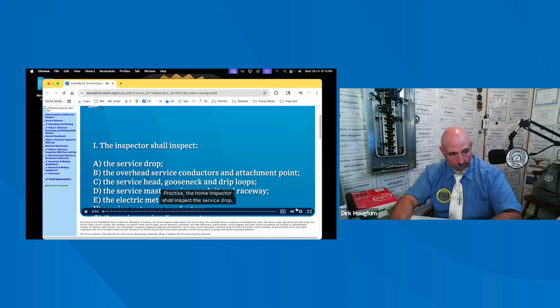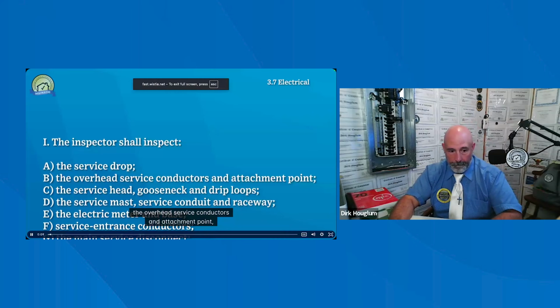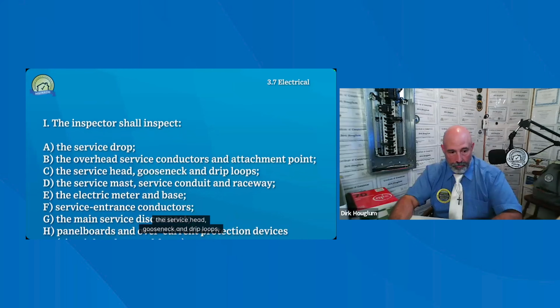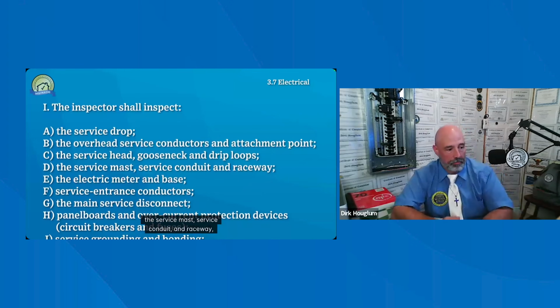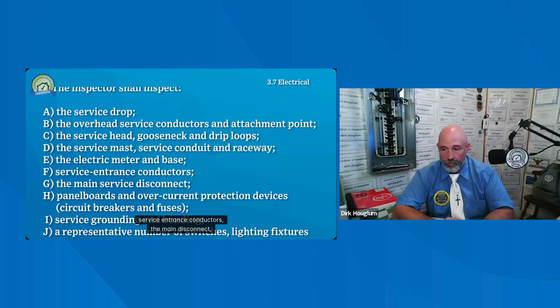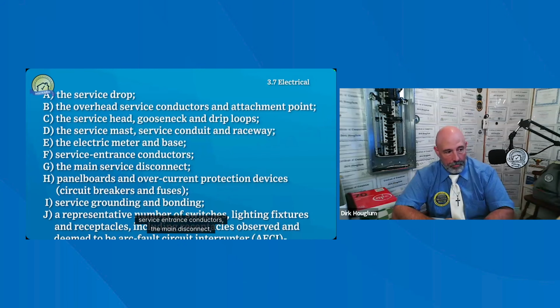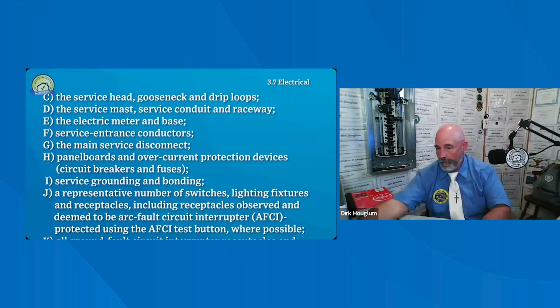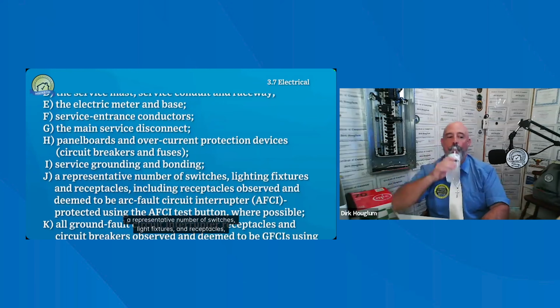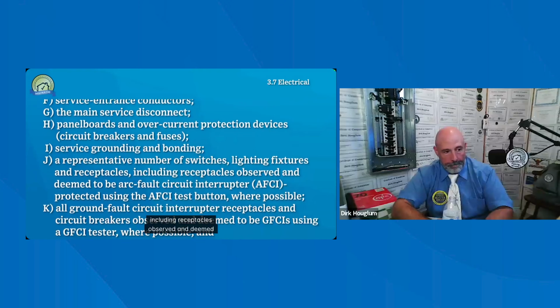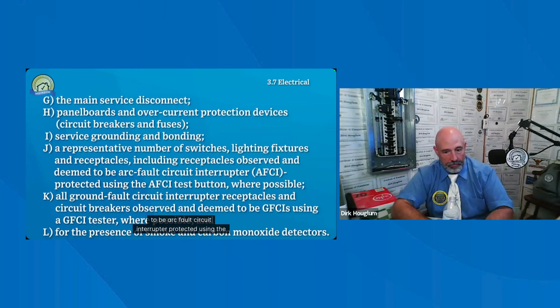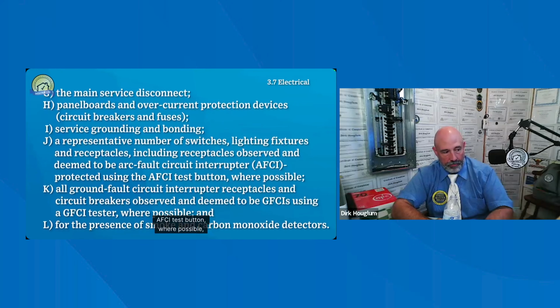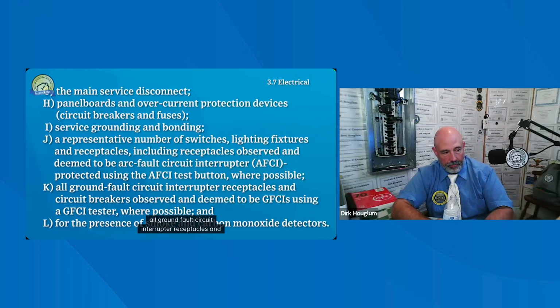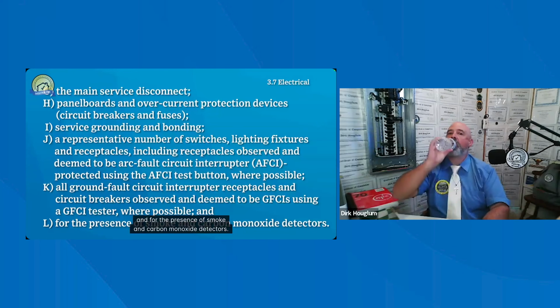The home inspector shall inspect the service drop, the overhead service conductors and attachment point, the service head, gooseneck and drip loops, the service mast, service conduit and raceway, the electric meter and its base, service entrance conductors, the main disconnect, panel boards, circuit breakers and fuses, service grounding and bonding, a representative number of switches, light fixtures, and receptacles, including receptacles observed and deemed to be arc fault circuit interrupter protected using the AFCI test button where possible, all ground fault circuit interrupter receptacles and circuit breakers observed and deemed to be GFCIs using a GFCI tester where possible, and for the presence of smoke and carbon monoxide detectors.